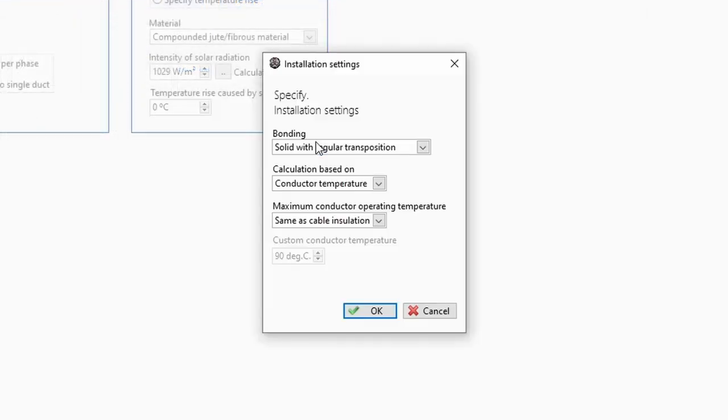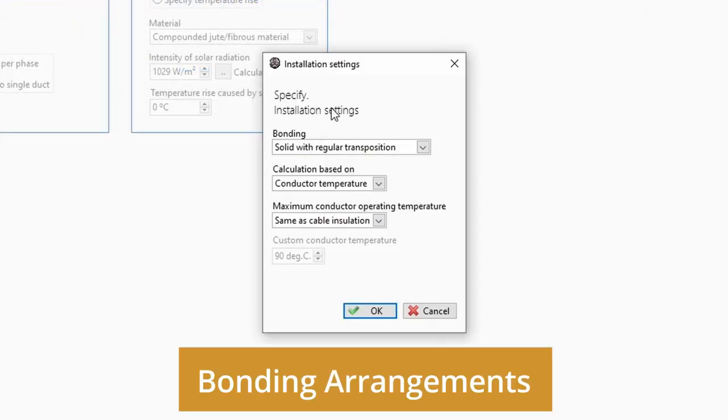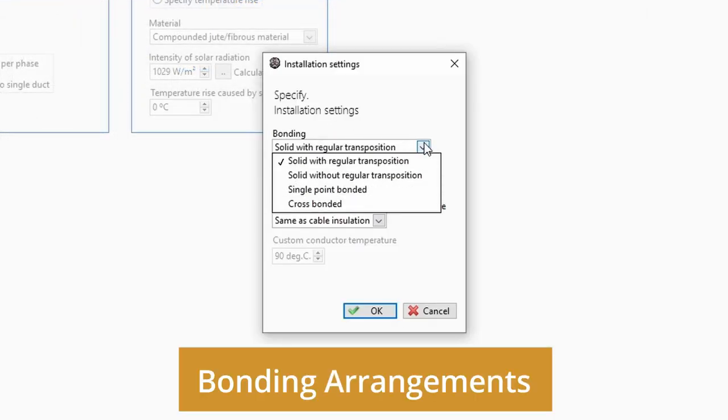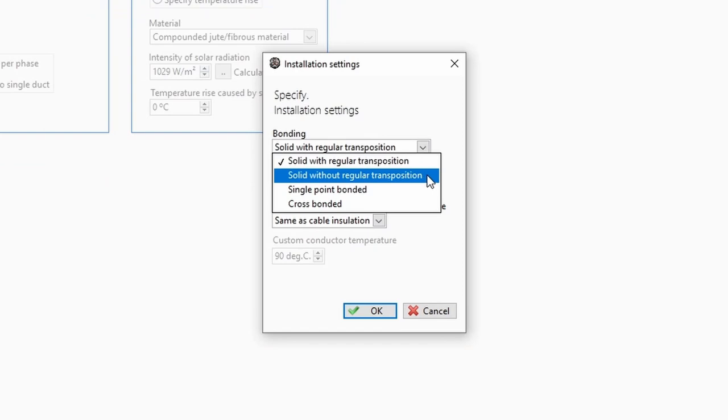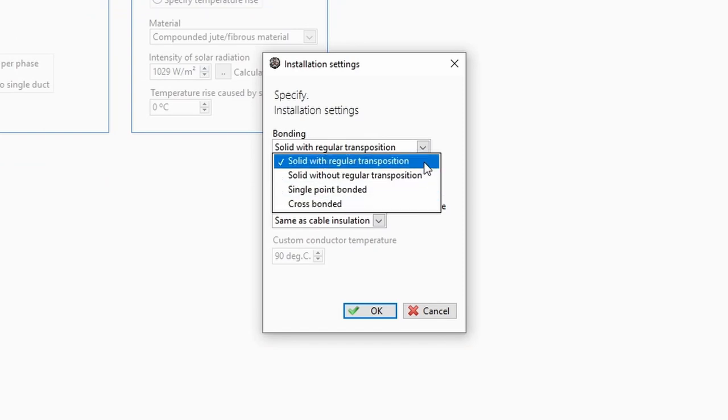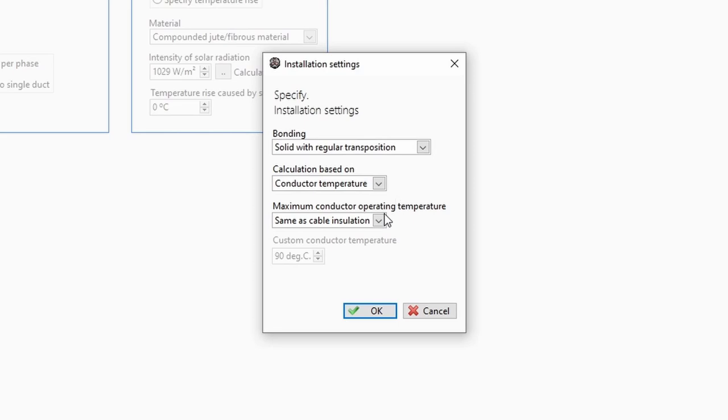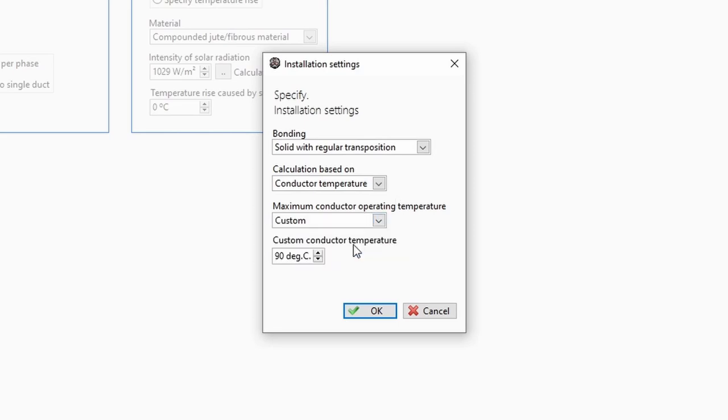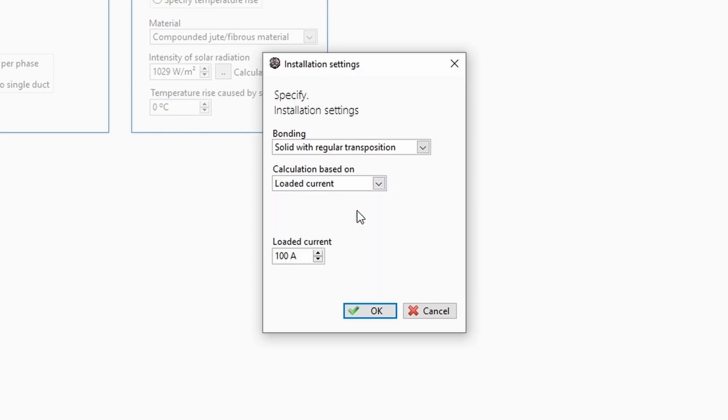Cable bonding arrangements can be changed between solid with or without regular transposition, single point, or cross bonded. Cable operating temperature may be customized or circuits given a fixed current.